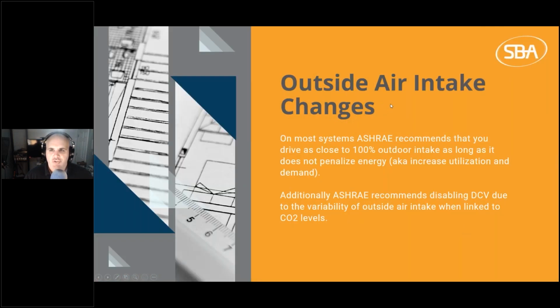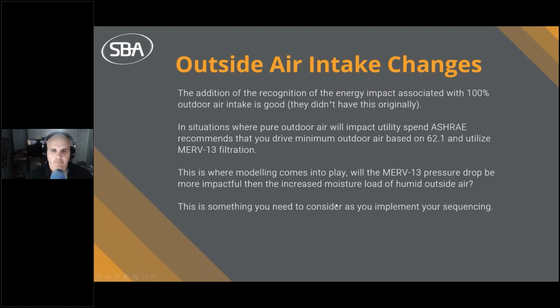All right, so outside air intake changes. On most systems, ASHRAE is going to recommend that you drive as close to 100% outdoor air intake as long as it does not penalize energy, also known as increased utilization and demand. Additionally, ASHRAE is going to recommend disabling demand control ventilation due to the variability of outside air intake when linked to CO2 levels. All right. The addition of the recognition of the energy impact associated with 100% outdoor air intake, in my opinion, is good. They didn't really have this originally.